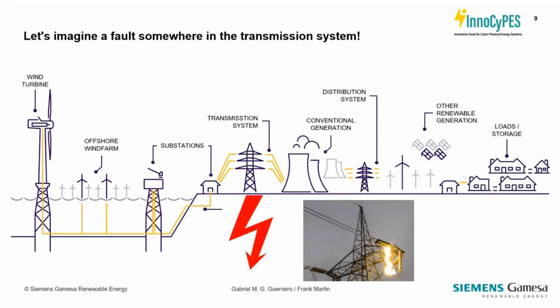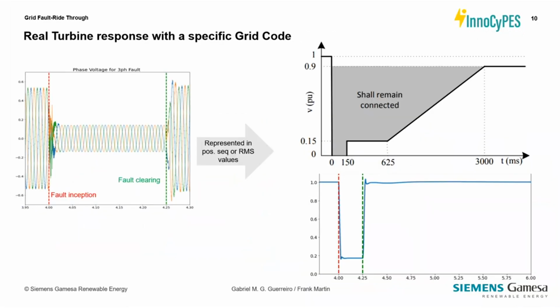Imagine that's a fault that happened here. This is not a fault in the offshore wind farm, nor close by, but as an important generation source in the system, this wind farm needs to sustain and remain connected during the fault. This is what we call fault ride through, which is basically required by grid codes, specific requirements from different countries on how you should behave during a fault.